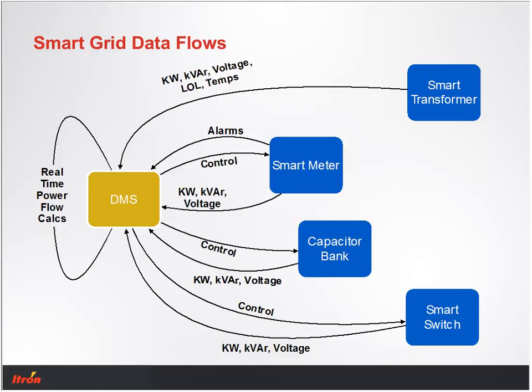So here's where our smart transformers come into play. The smart transformers are streaming back kilowatts, kVARs, voltage, loss of life, and temperature so that we have a complete understanding of load at all of the points on the feeder. We also have the smart meters now bringing us the same measures at the household level, but with control, of course, to connect or disconnect the meter, and with remote interrogation capability, alarms that tell us about events that have occurred on the meter. That's a very key thing that we'll get into here shortly. And we have cap banks, which are also controllable, bring back the kilowatts, kVARs, and voltage. So we've got those primary measures at multiple points on the feeder.